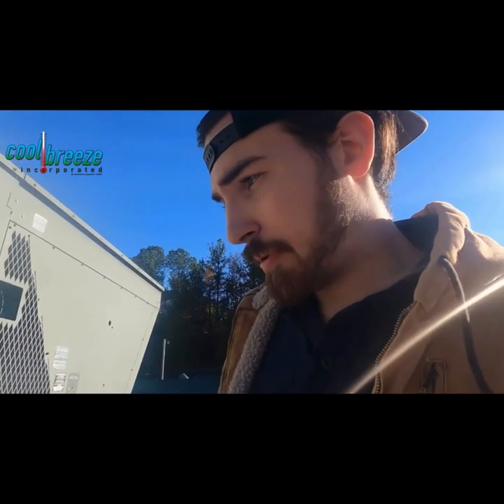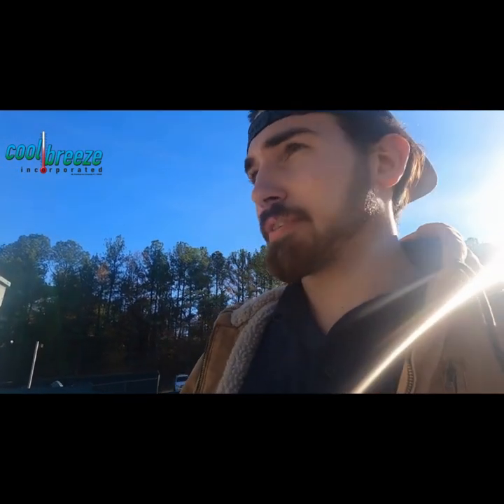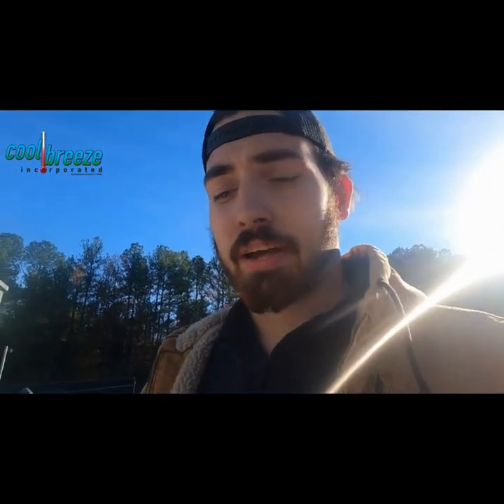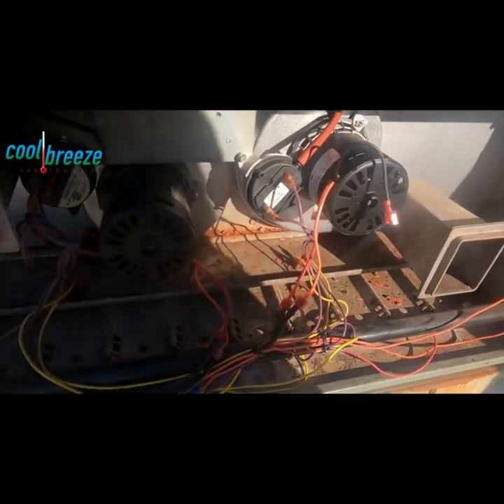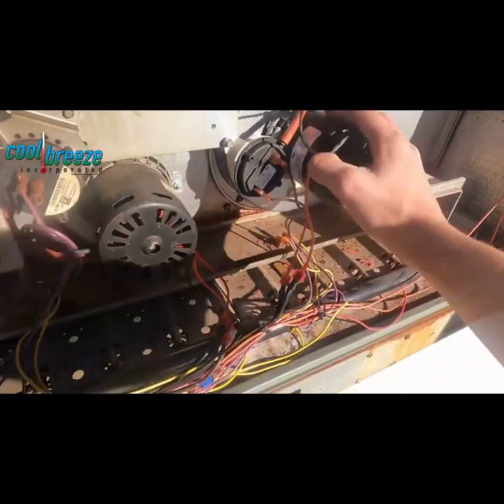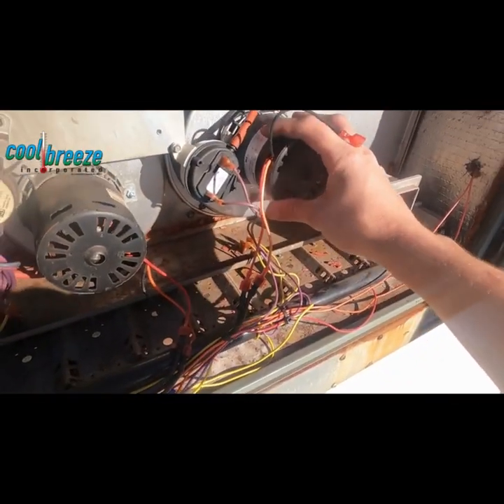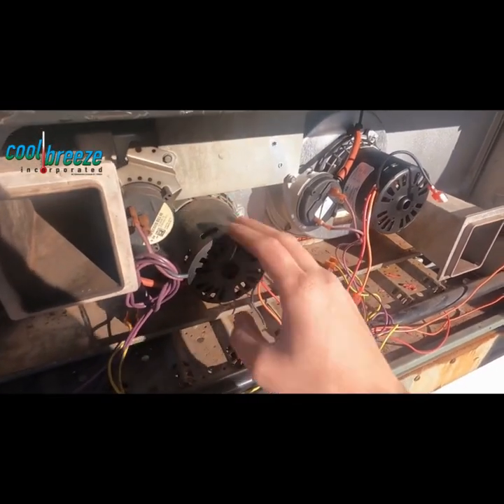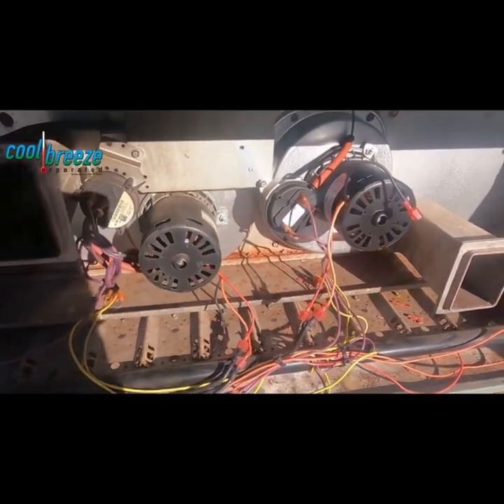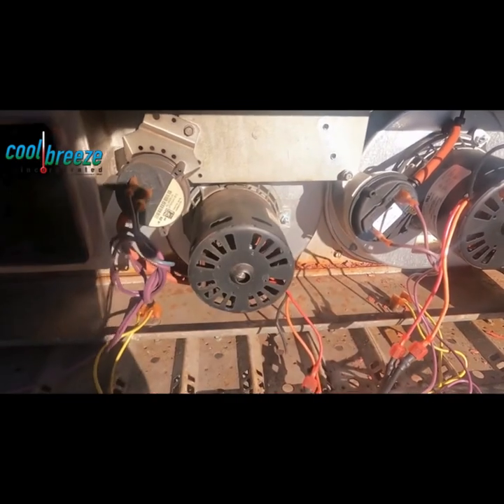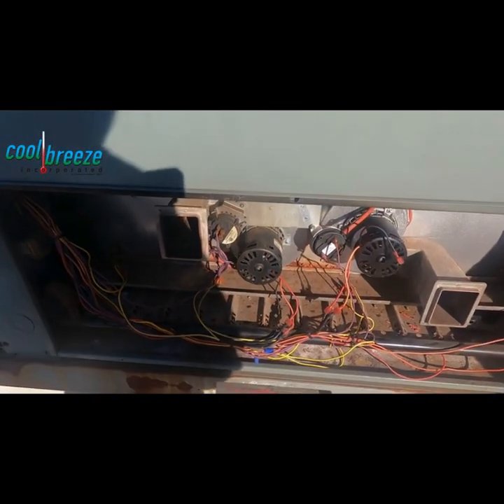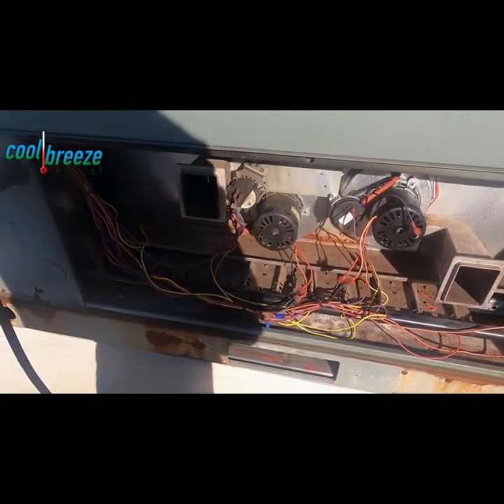What we're going to be doing today is replacing the inducer draft motor assembly on a Rheem gas pack. As you can see, on a previous visit we already replaced this one. This is the one that has failed on this call. I already diagnosed it; it's bad, seized up mechanically. So right now you're going to watch me replace it.